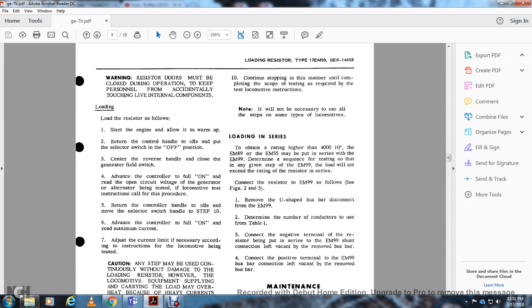Connect the resistor to the EM99 as follows. See figures 2 and 5 and remove the U-shaped bus bar disconnect from the EM99. Determine the number of conductors to use with table 1. 3. Connect the negative terminal of the resistor being put in series to the EM99 shunt connection left vacant by the removed bus bar. 4. Connect the positive terminal to the EM99 bus bar connection left vacant by the removed bus bar.